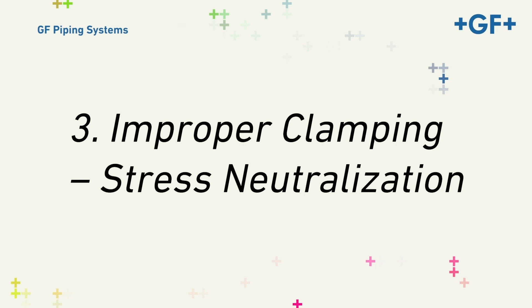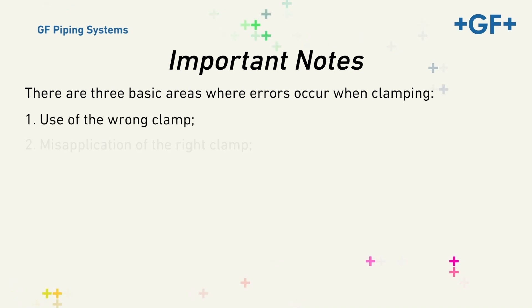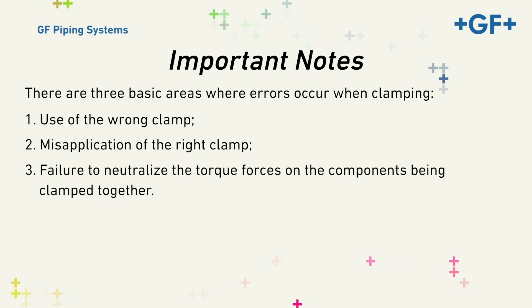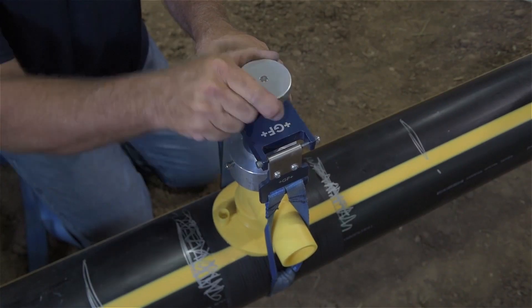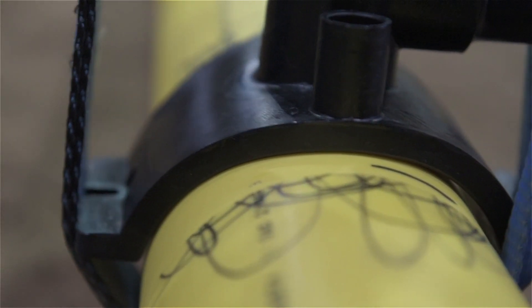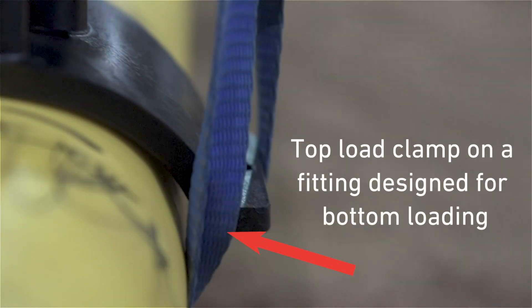Three, Improper Clamping and Stress Neutralization. There are three basic areas where errors occur when clamping: use of the wrong clamp, misapplication of the right clamp, and failure to neutralize the torque forces on the components being clamped together. It is essential for operators to use the clamping system designed by the manufacturer for the fitting being installed. Sidewall fittings come in two basic designs: bottom load and top load. Never use a top load clamp on a fitting designed for bottom loading. A top load clamp pulls the side of the fittings down against the pipe; as a result, the base of the bottom load fitting sets loosely on the pipe until the clamp conforms it.